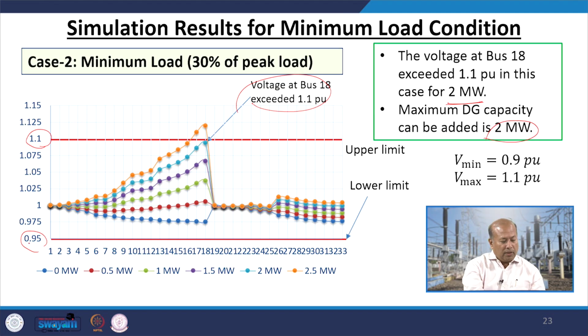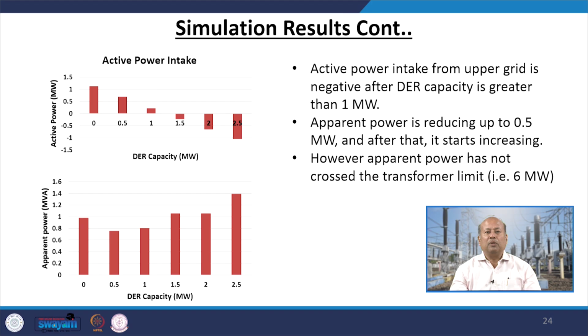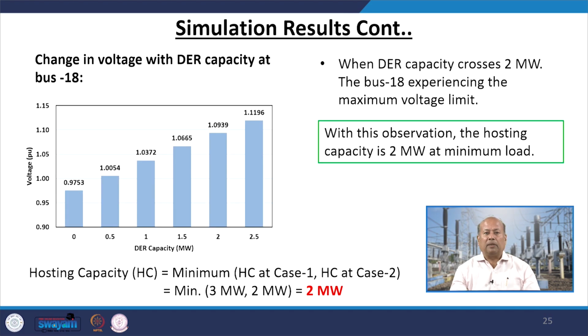So, there is a small correction. This can be my 0.9 per unit. Simulation results: you can see that active power intake from the upper grid is negative after DER capacity is greater than 1 megawatt. Apparent power is reducing up to 0.5 megawatt, and after that it starts increasing. However, apparent power has not crossed the transformer limit of 6 megawatt.